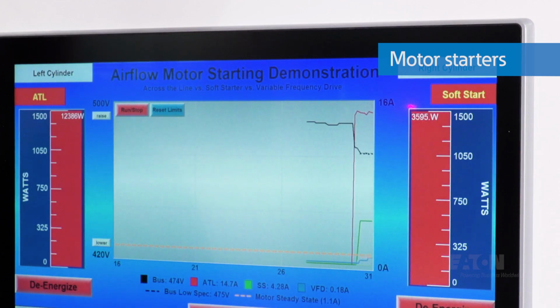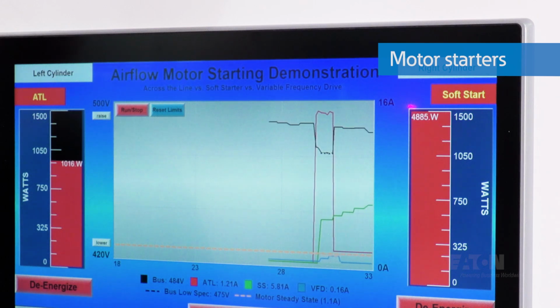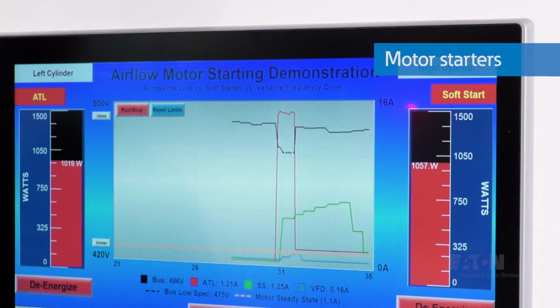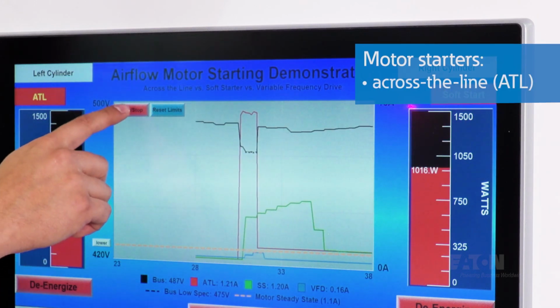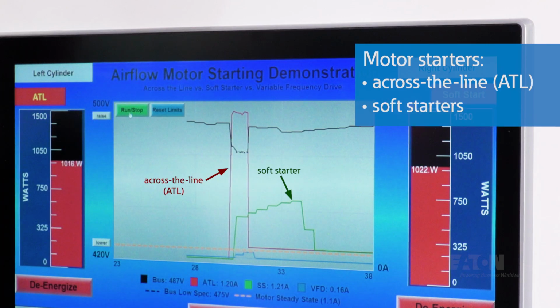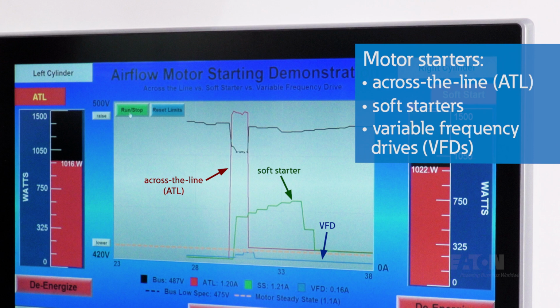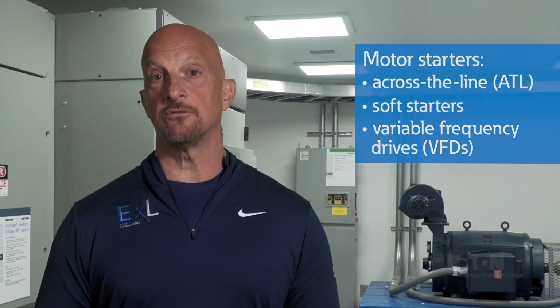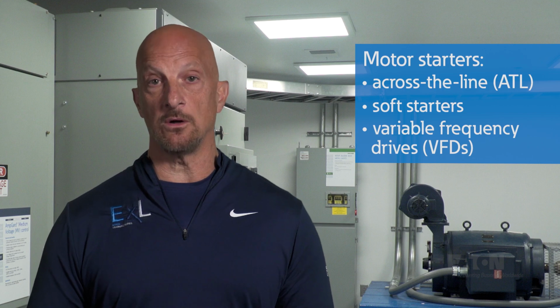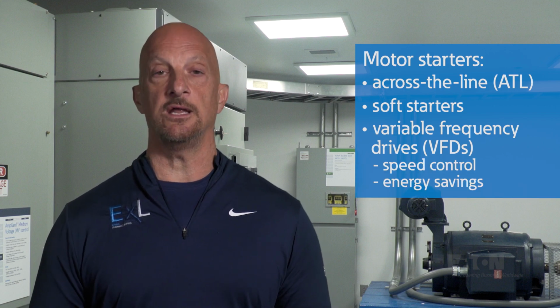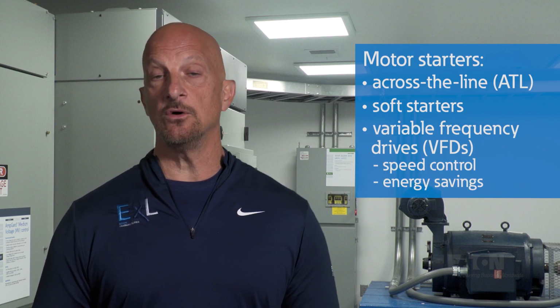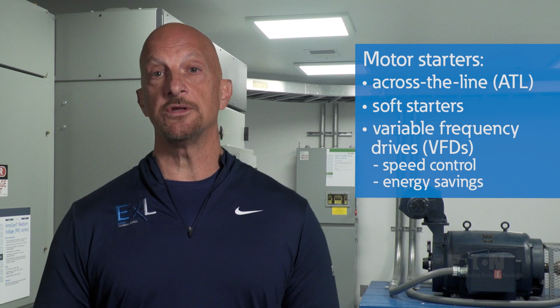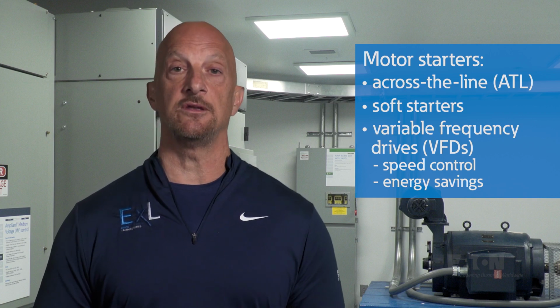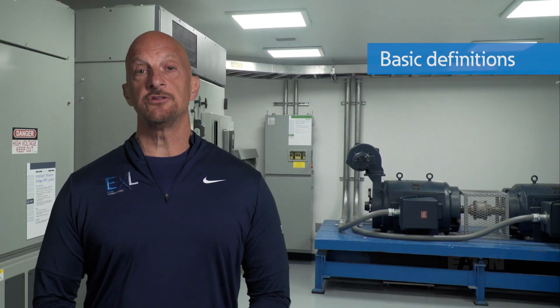There are 3 types of motor starting methods, and each has an effect on inrush current and the associated voltage drop: across the line, or ATL; soft starting, also called reduced voltage starting; and variable frequency drives, or VFDs. Once the motor is started, VFDs can offer significant operating benefits as well, including speed control and energy savings. In this video, we'll cover considerations, risks, and cost benefits of each method. Let's start with a simple explanation of each.